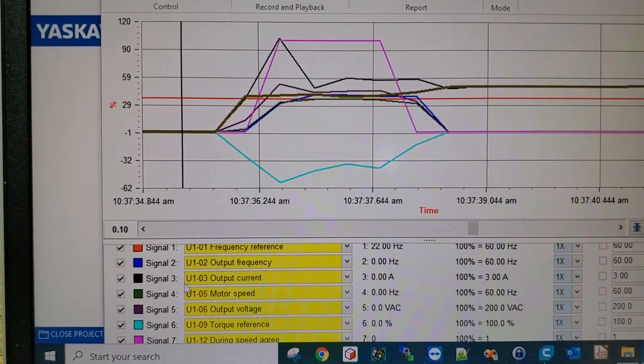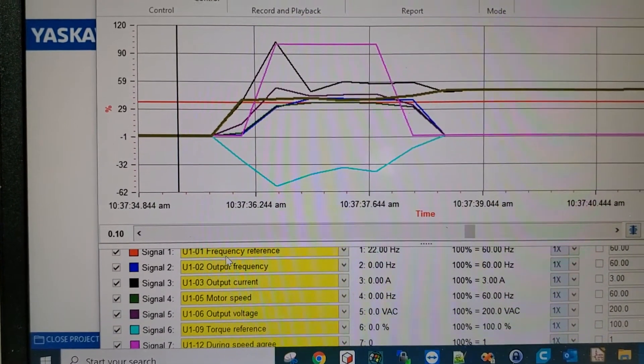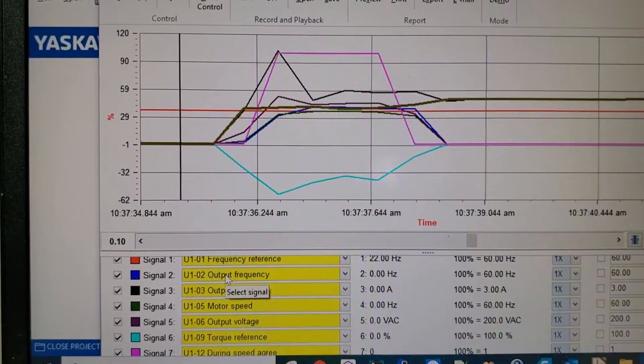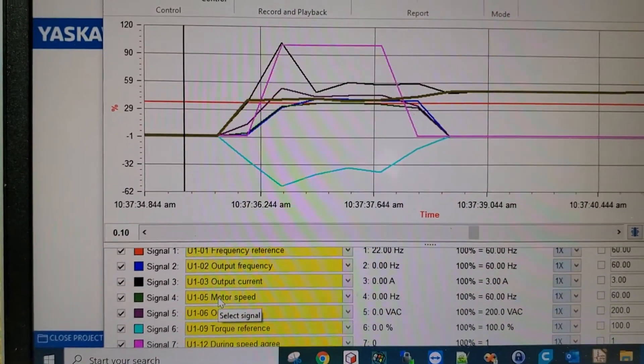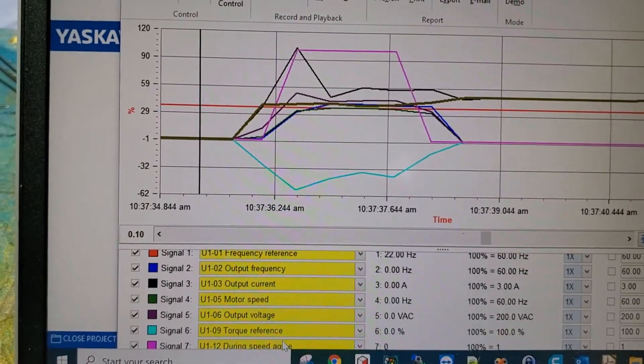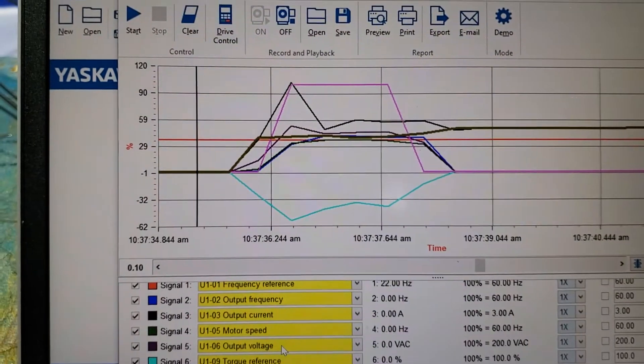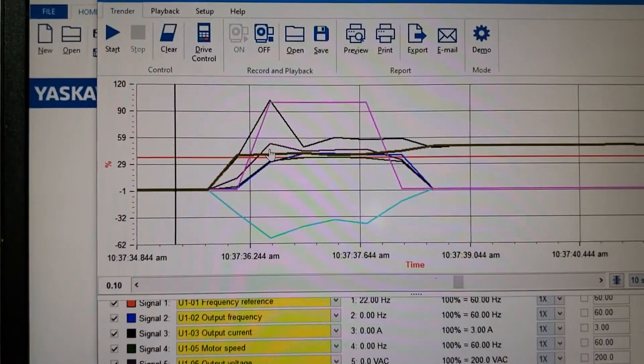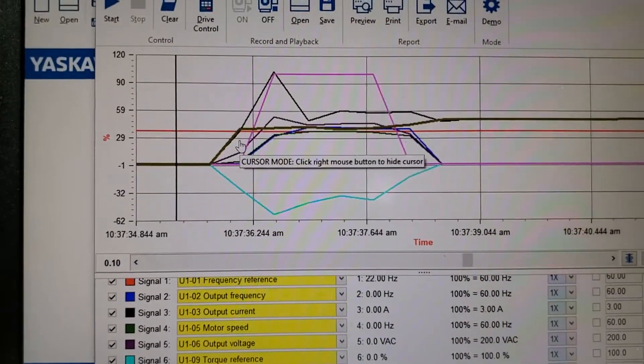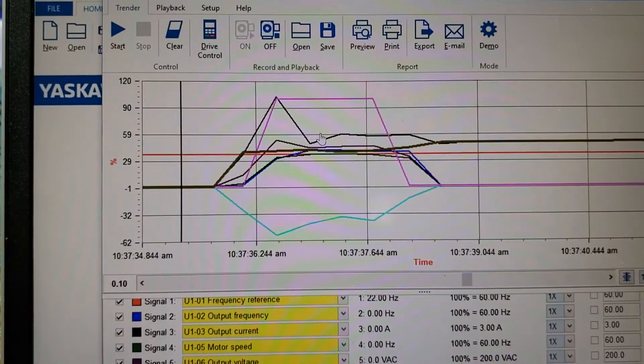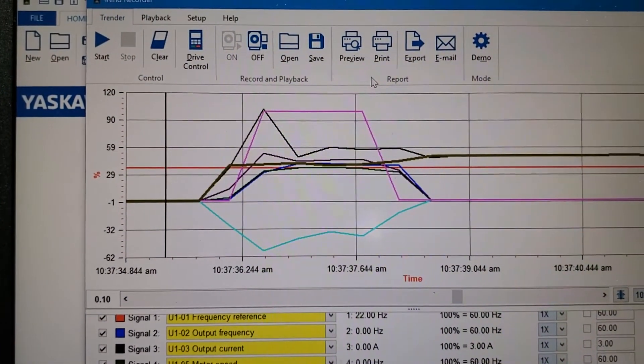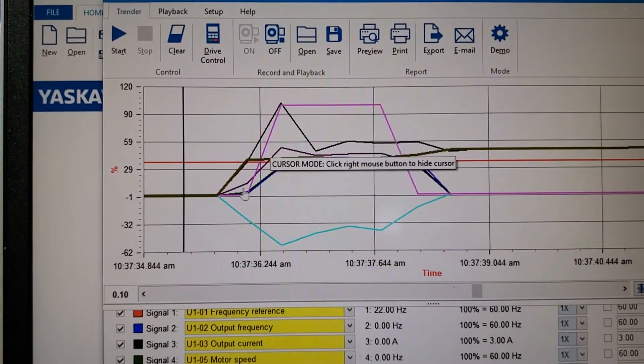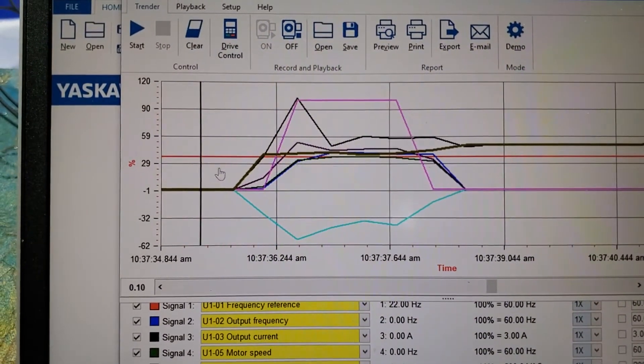What we're telling it to run at, what it's outputting that it's running at, what it's calculated the motor is actually running at, torque reference, output voltage and current, when speed agree happens - so when it thinks it's at the point that it's controlling the speed accurately based on the load. At any point, if you click on this line, it will show you what the actual values are.